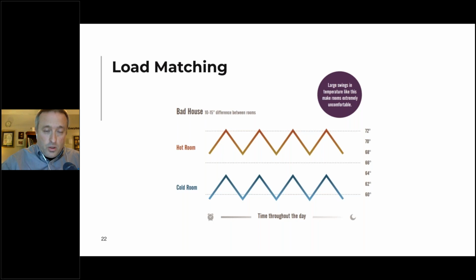This shows what you normally see. When equipment is oversized, the temperature goes up very quickly, and if the house is leaky, it comes down very quickly too. In a poorly balanced house, or one with leaky or poorly insulated rooms, it's not uncommon to see 10 to 15 degree differences from one room to another. This is an uncomfortable house, with temperature racing up and down. This is not what you want to see.